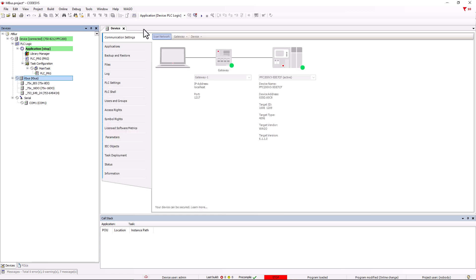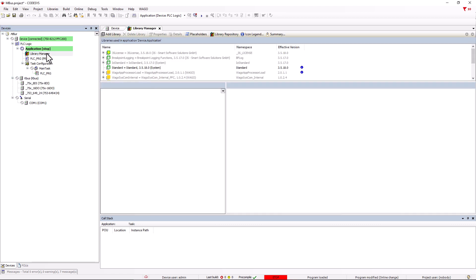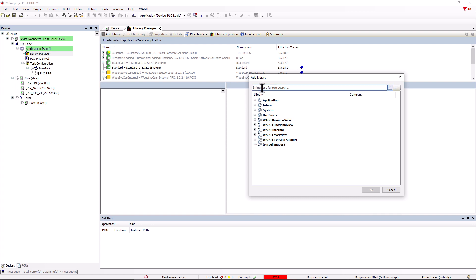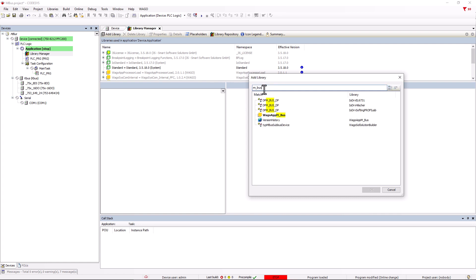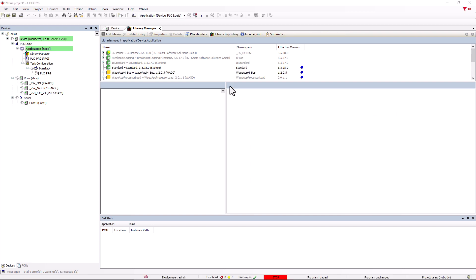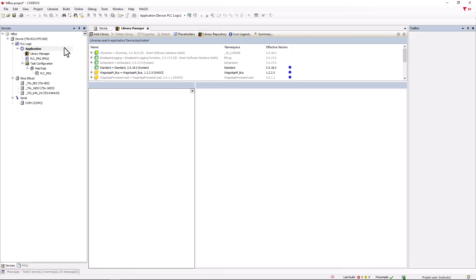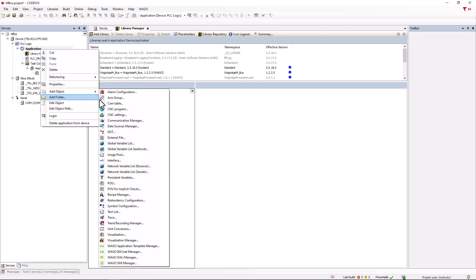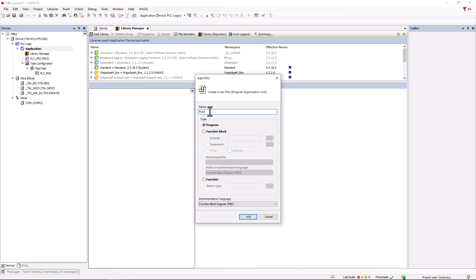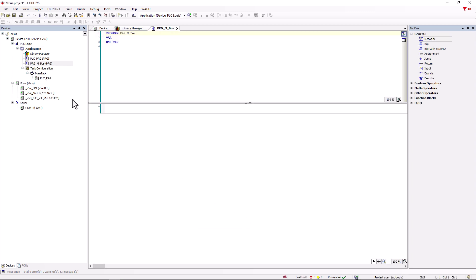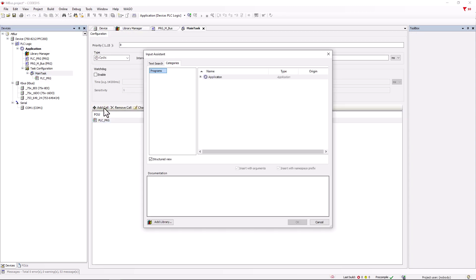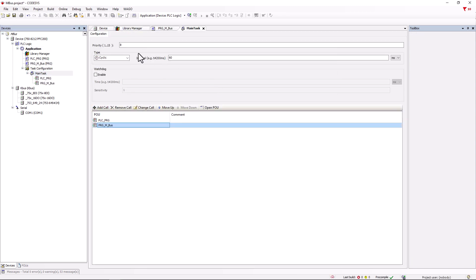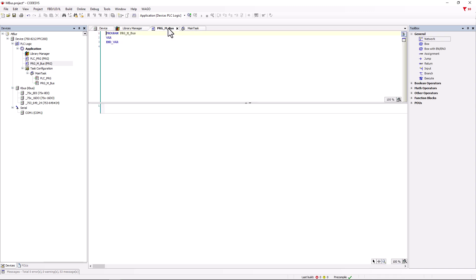In the Library Manager, we add the WAGO MBUS app. We create a new program and call it up in the main task. For MBUS applications, a priority between 6 and 14 that is not in the background, and an interval time between 30 and 80 milliseconds are recommended.